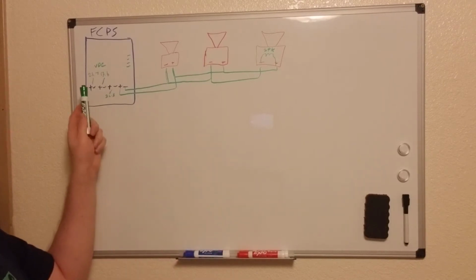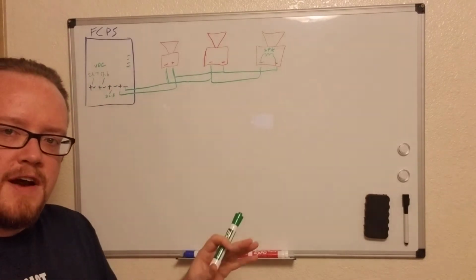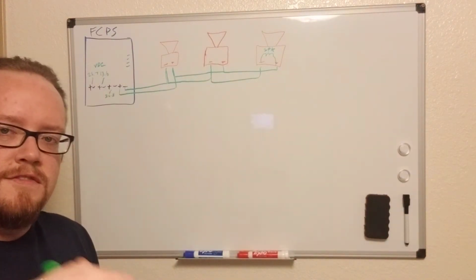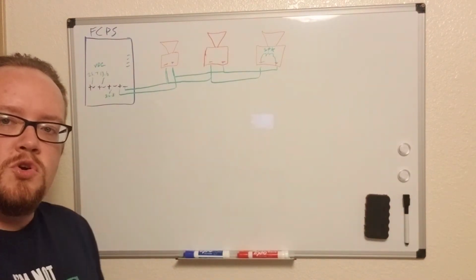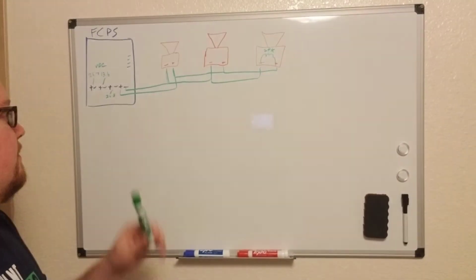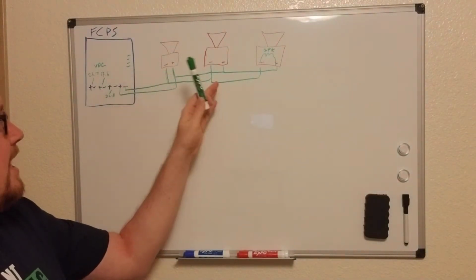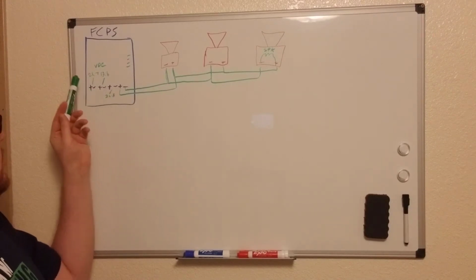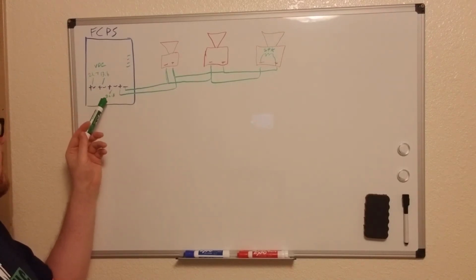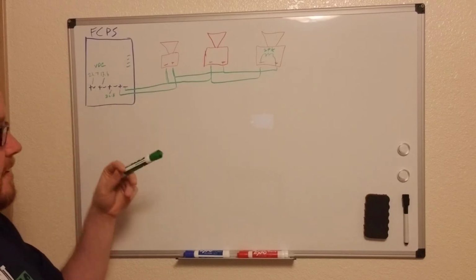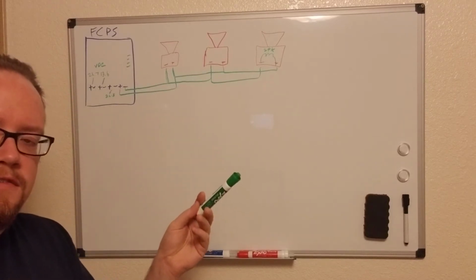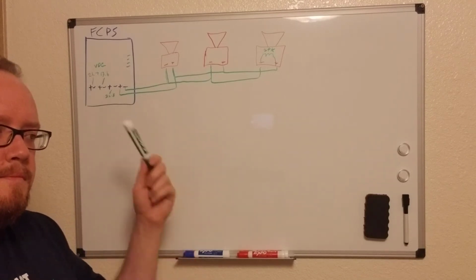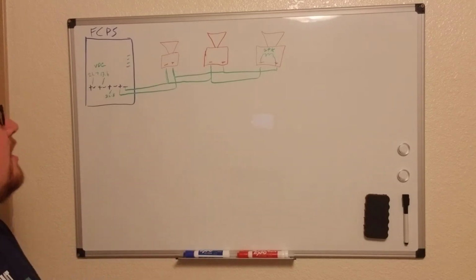Because every NAC panel, every manufacturer, brand is going to have their own consistent voltage when the system is normal. When the system is intact and you have a resistor at the end of the line, you're going to see, we'll say, 26.7 to 27 point something. There's going to be a couple of voltage difference, but they're all going to be in a certain range for that model and that manufacturer.